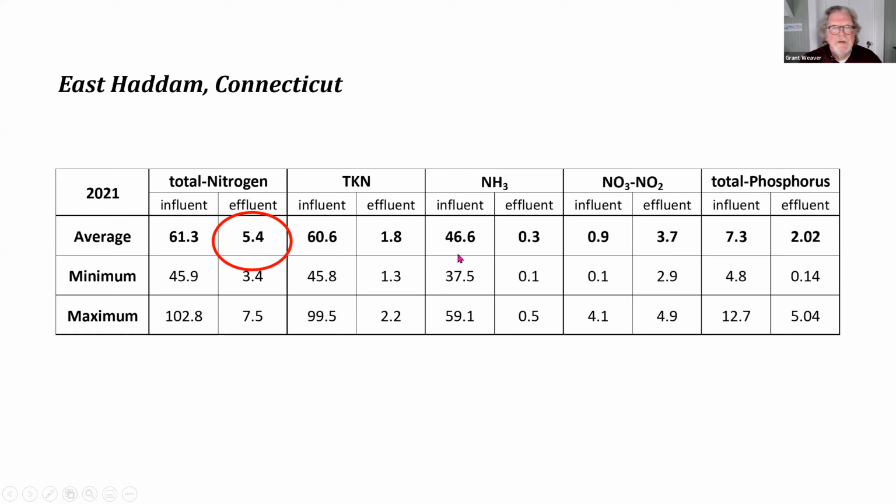Here we do have the breakdowns, consistently good ammonia removal. TKN would be the difference between that 1.8 and the 0.3, which is 1.5, if my arithmetic's correct. That would be organic nitrogen, not much chance removing that. The majority of the nitrogen is nitrite.